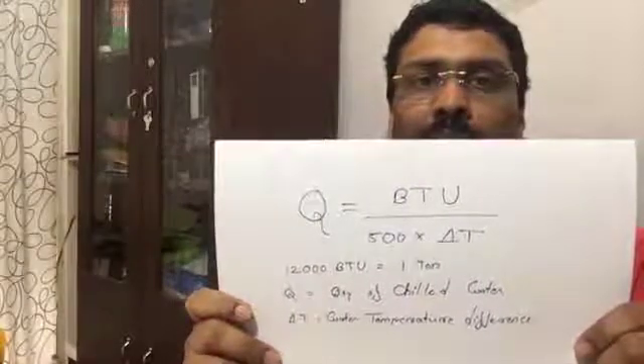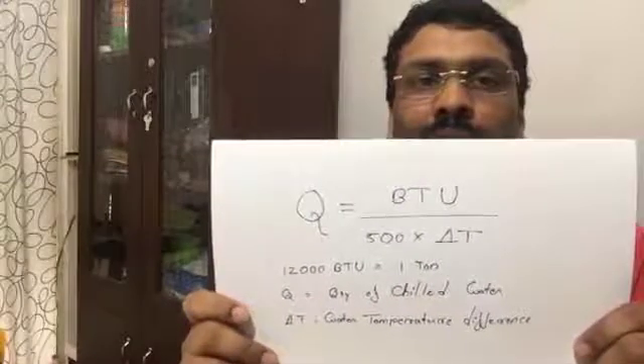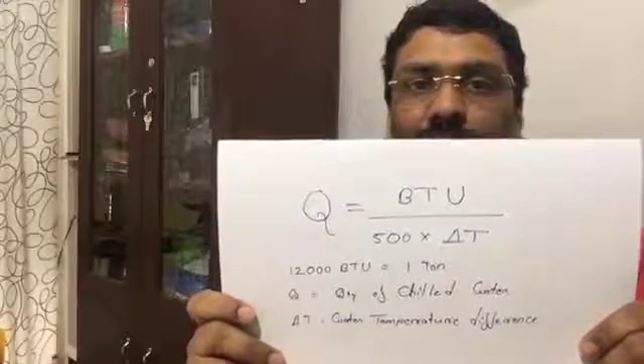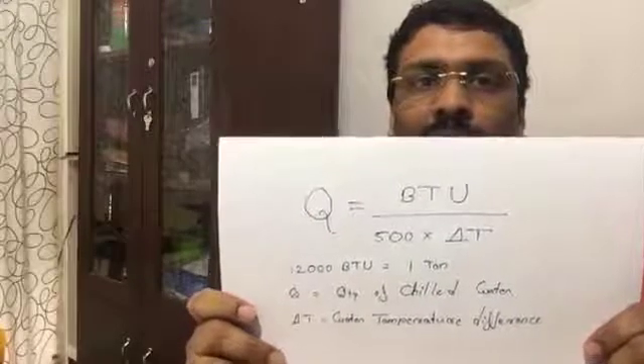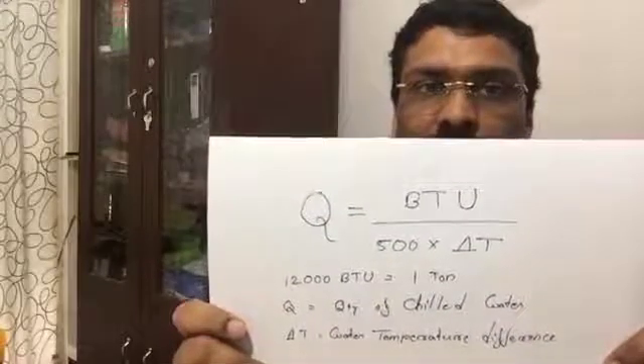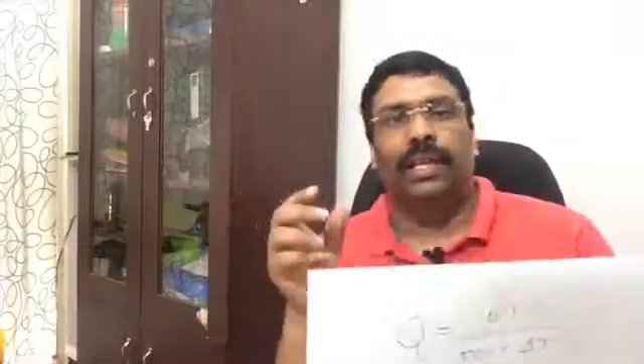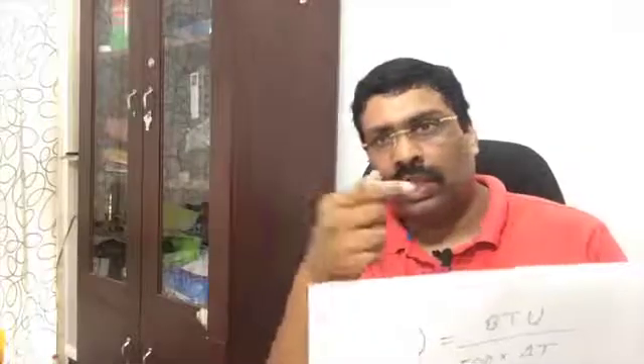BTU — British Thermal Unit. 12,000 BTU is equal to 1 ton, and Q is of course the quantity of chilled water. Delta T means the difference between the supply chilled water temperature and the return chilled water temperature — that is called delta T.